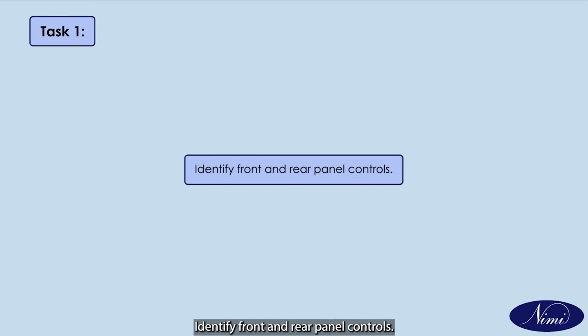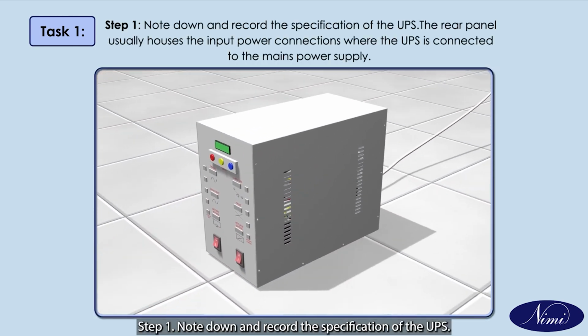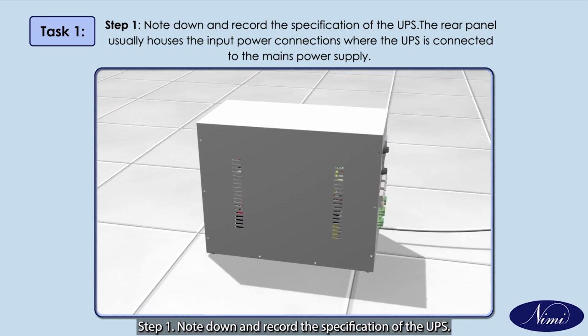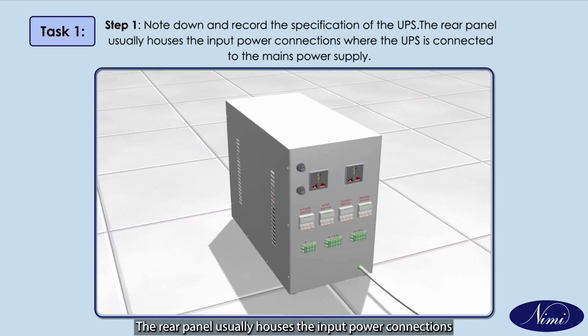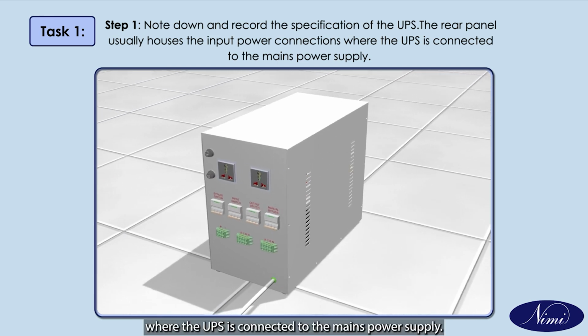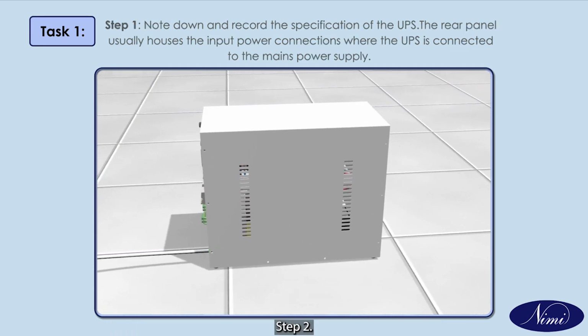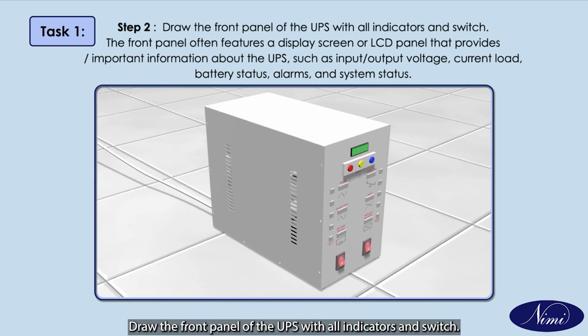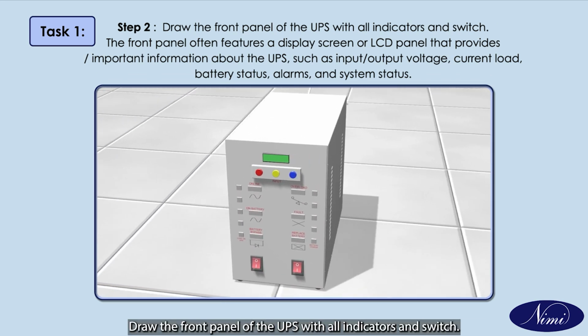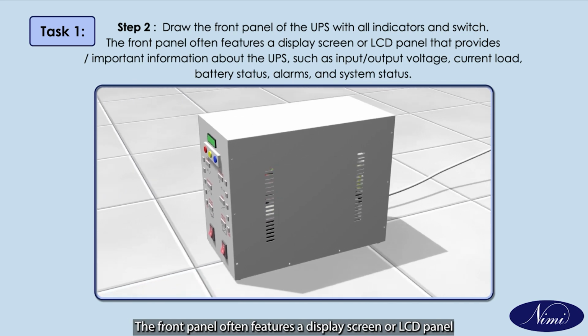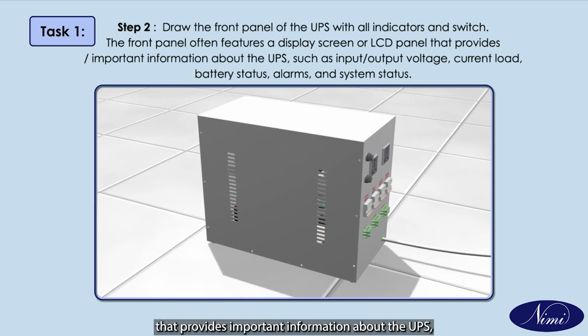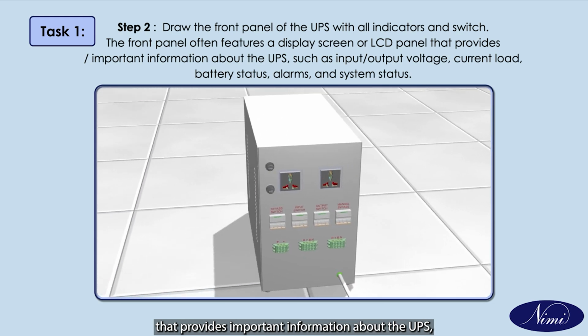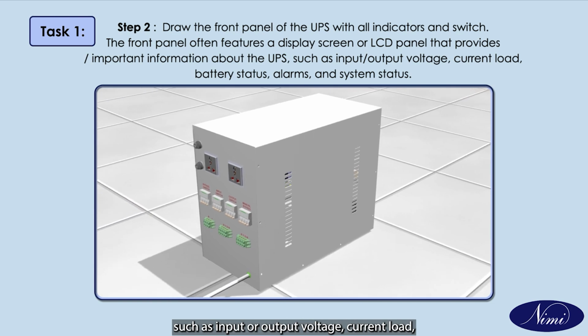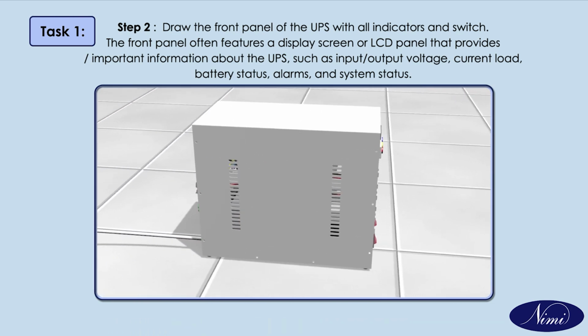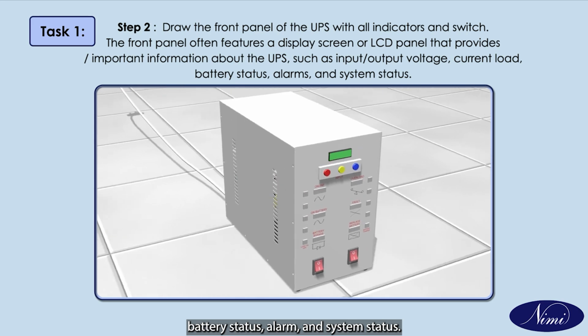Procedure. Task 1. Identify front and rear panel controls. Step 1. Note down and record the specification of the UPS. The rear panel usually houses the input power connections, where the UPS is connected to the mains power supply. Step 2. Draw the front panel of the UPS with all indicators and switches. The front panel often features a display screen or LCD panel that provides important information about the UPS, such as input or output voltage, current load, battery status, alarms, and system status.